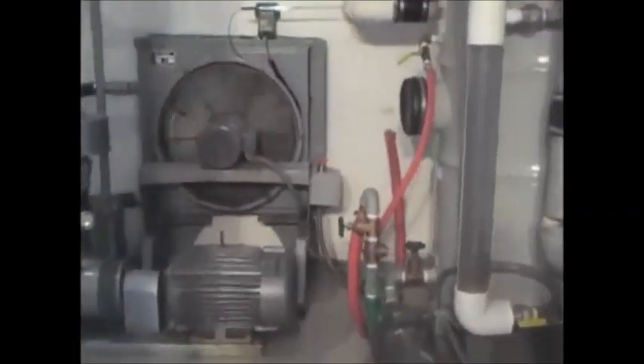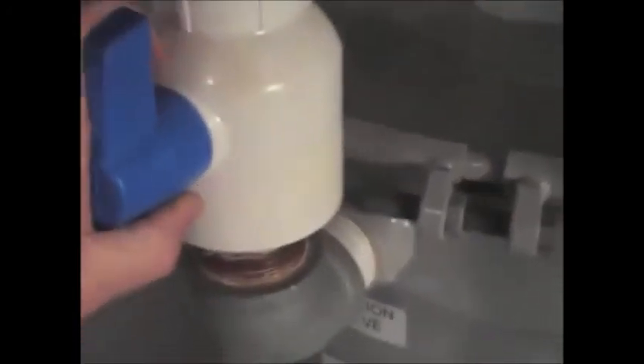One thing I did want to point out is that you can actually see that now with pulling water, our anemometer is reading over. It will only read about 300 CFM with a 3-inch pipe on it, so the instrumentation will have to be worked out. Whatever kind of flow you're looking for will have to be worked out. But you can increase the flow and get, of course, well over 300 if you close the dilution on the intake filter here. So that's about all I wanted to say at this point.